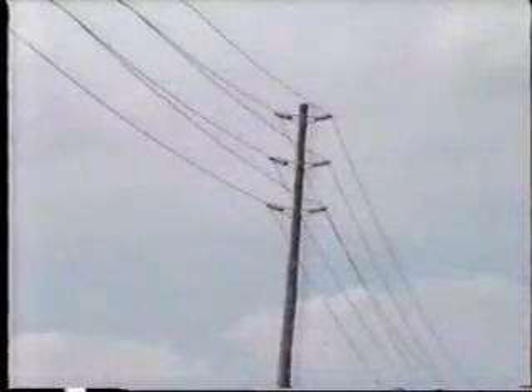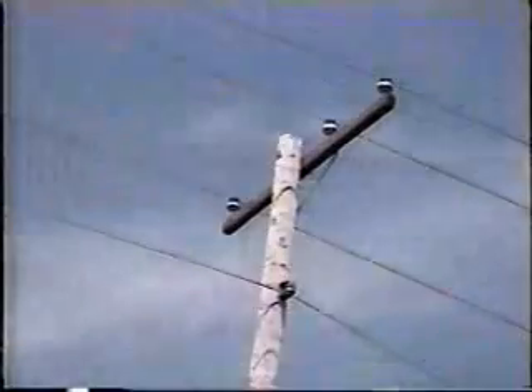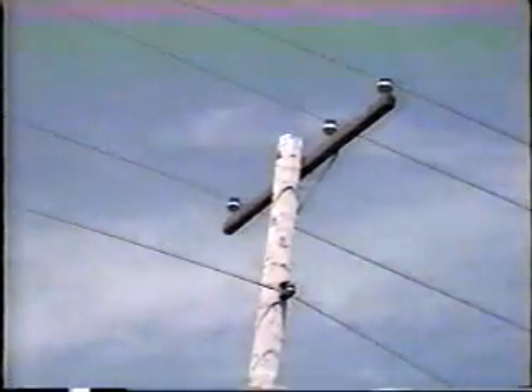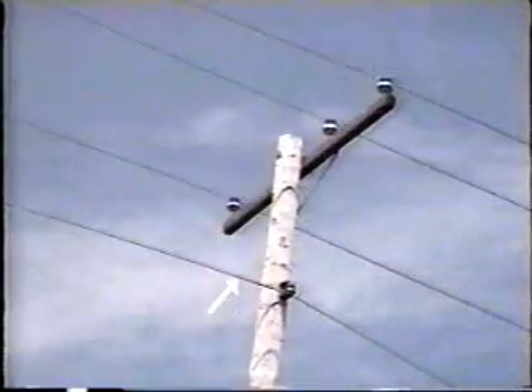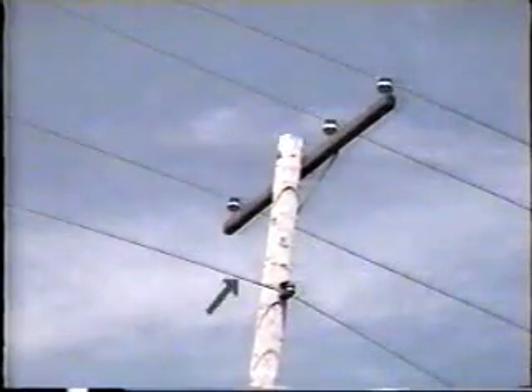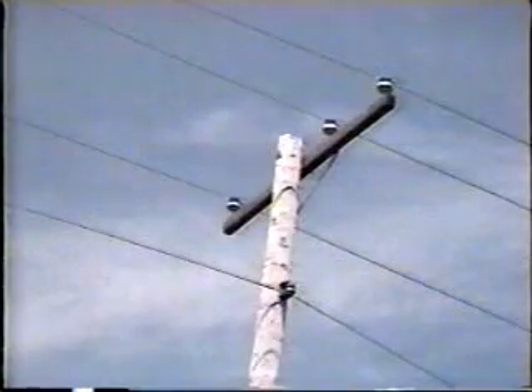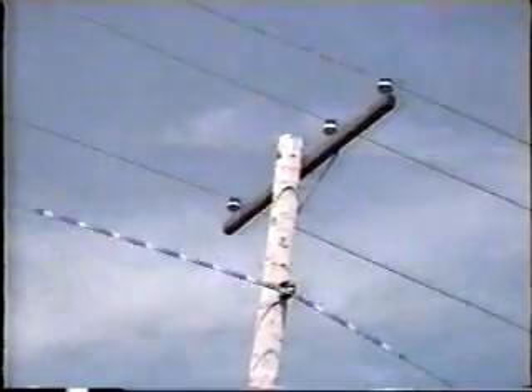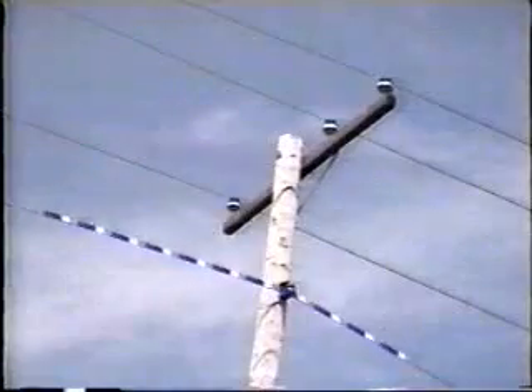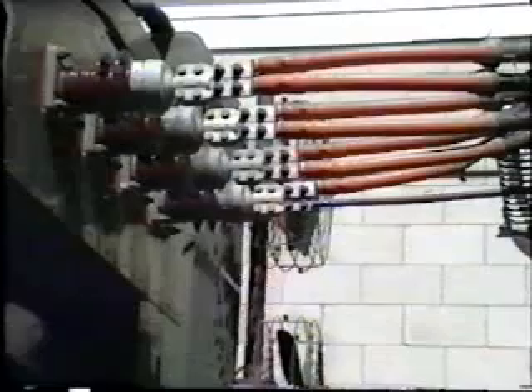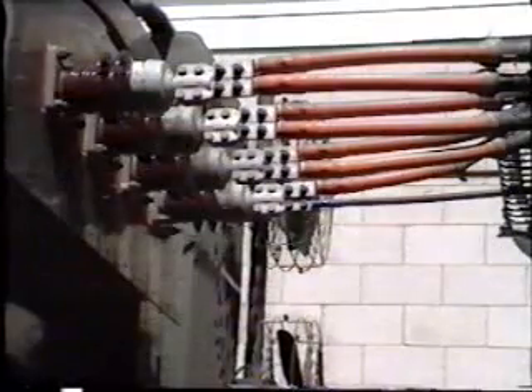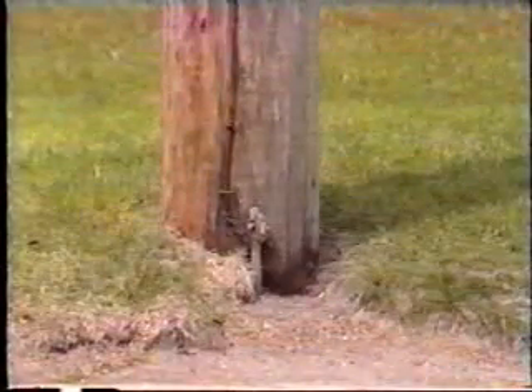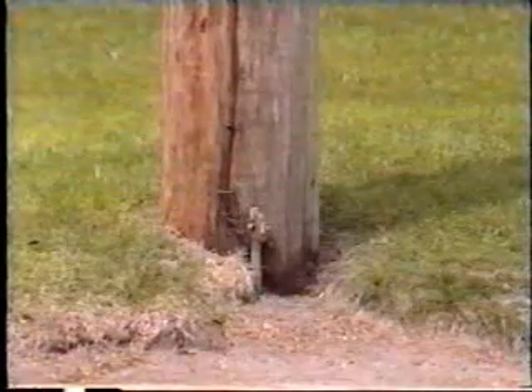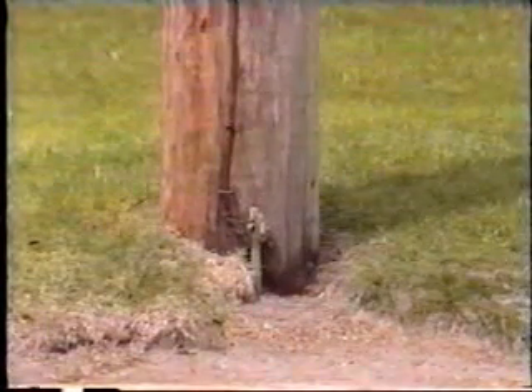The conductors may be delta connected, that is, with no neutral, but more often than not they are Y connected with a neutral running along the same support structures. The loads across the three phases are often out of balance, so that some current normally flows along the neutral. The neutral is usually connected to ground at the source transformer, and additionally by connection to the grounding straps, which run down intermittent poles into ground.